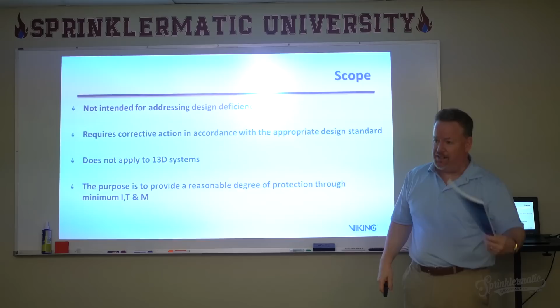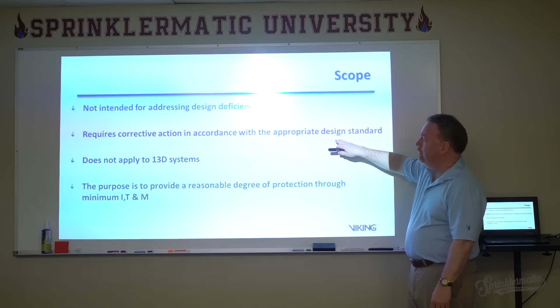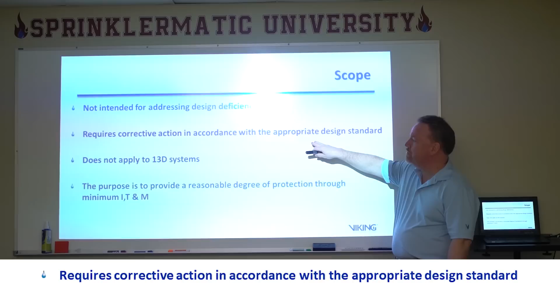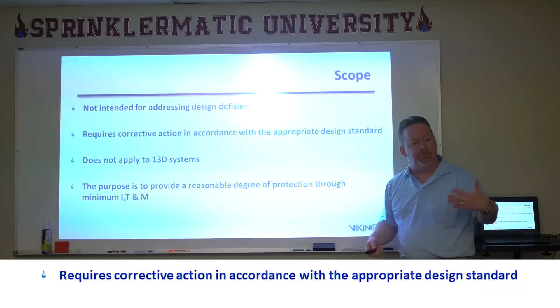Why? Because they've got the fire code behind them, and the fire code says you will have a properly sprinklered building, basically. So the scope requires corrective action in accordance with the appropriate design standard. If we find a problem and we see that it needs to be corrected, NFPA 25 is not the document that says here's how you correct it. So you have to go back to the design standard. If we find problems, you're usually going back to the design standard to figure out what the correct answer is.